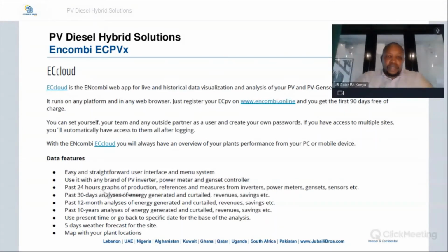In terms of monitoring, you can get graphs of production references and measurements from inverters, power meters, generators, and sensors. That is on a 24-hour period, as well as a 30-day analysis of energy generation, how much energy was generated, how much energy was curtailed, as well as the revenues and savings. You can have 12-month analyses, again of energy generated or curtailed, as well as revenues and savings, and the same for 10 years. So in terms of monitoring, you can get a ton of information on how your PV diesel hybrid is working.